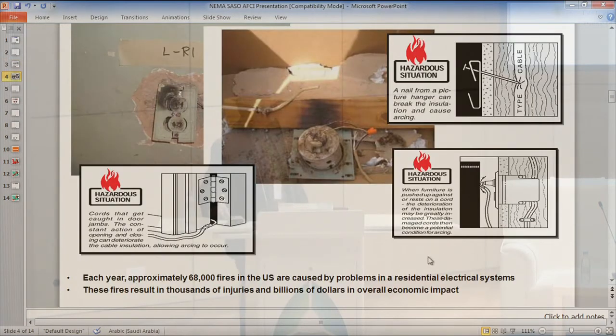What we protect against when we're using an arc fault circuit breaker is basically these situations where in a lot of cases you have cords and stuff around the home that aren't protected for years and years, and they abrade, and the conductors start to come together in various ways, creating little sparks, which eventually lead up to a heating situation, which then can cause a fire. And I think we've each seen this in our lifetime where something very bad could have occurred or actually did occur as a result of this wear and tear on the wires or some change in the wiring that made the situation worse.